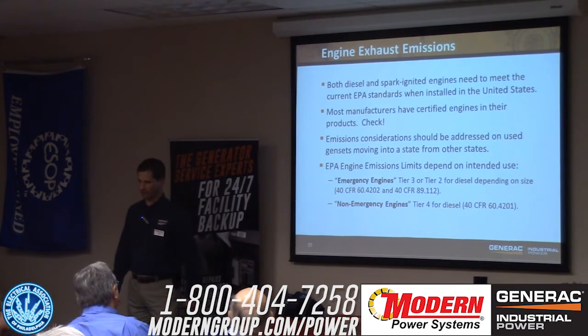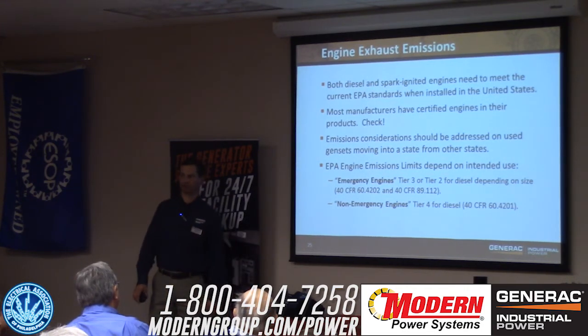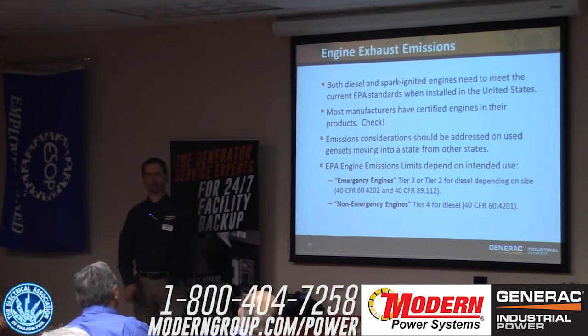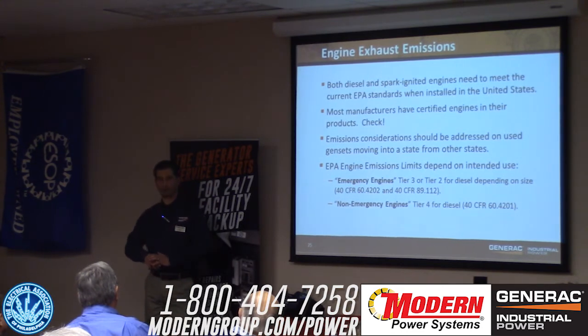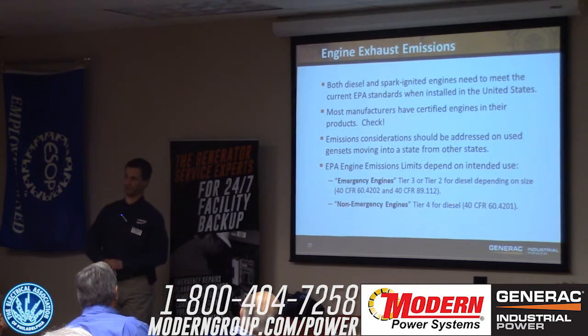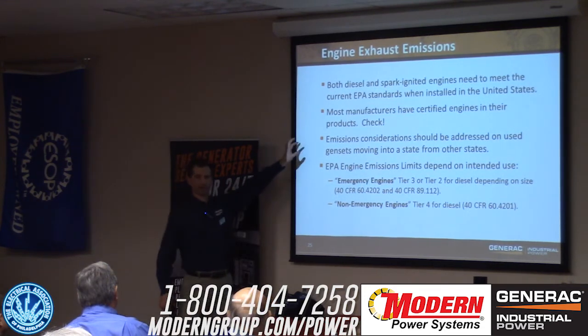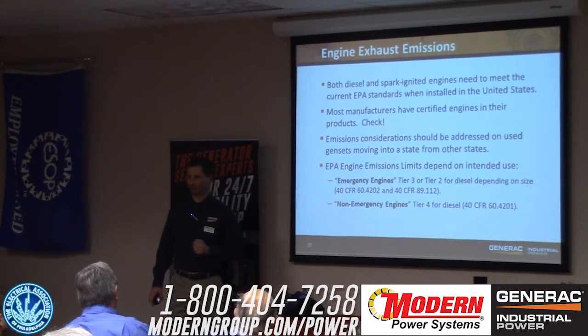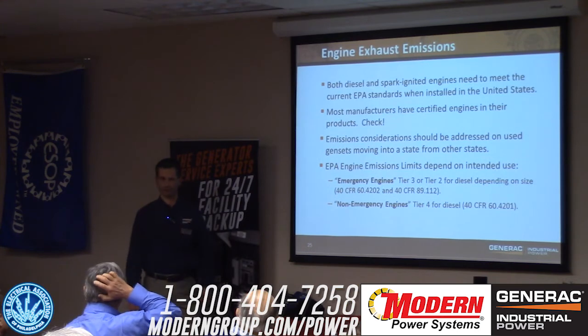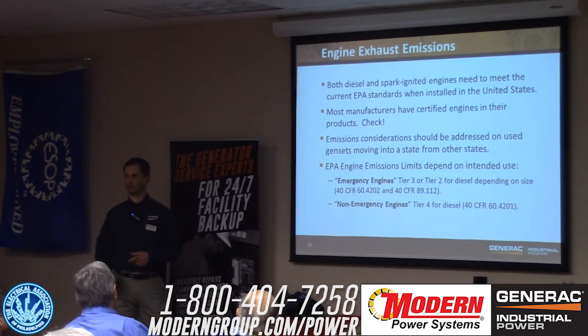We have a couple of 500 kW units out on the New Jersey Turnpike built by a competitor. I won't say the manufacturer, but they're green, and coming up on 3 years old. They're getting bills for about 15 grand apiece to do field emissions recertifications. If that engine comes out of the factory emission certified, the client never has to do that recertification, and that's a huge savings down the road, every 3 years.